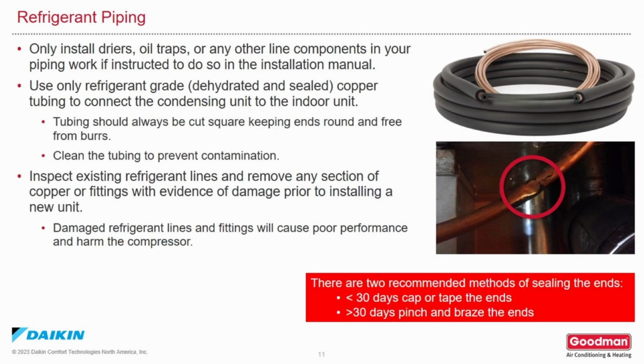When installing refrigerant piping, here are a few things to consider. Do not install dryers, oil traps, sight glass, or any other components in the refrigeration lines unless you're instructed to do so in the installation manual. Never install a suction line dryer on a heat pump. Only use refrigerant-grade copper tubing for your line sets. Make sure you have good, straight, clean cuts on the copper line, only made with a tubing cutter. Make sure the copper is clean to avoid contamination.